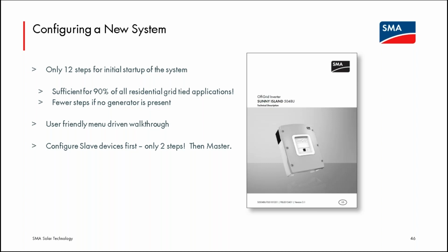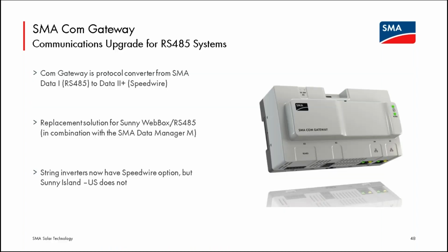I would strongly suggest setting that battery protection mode 1 trigger to 40%, 50%, something very, very high, where there's plenty of reaction time for a system operator to correct whatever problem is causing the protection mode to be entered before you get to protection mode 3. That is the tech tip video link there for walking through the quick configuration guide of the Sunny Island.